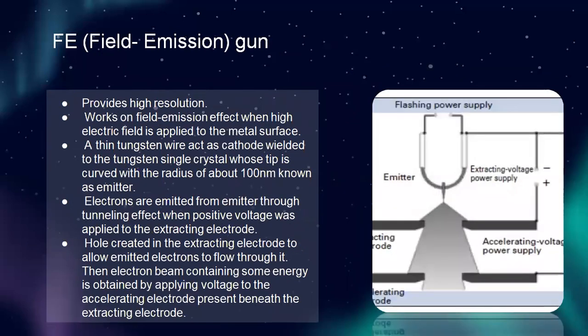The second type is the field emission gun, which provides high resolution work based on the field emission effect. When a high electric field is applied to the metal surface, a thin tungsten wire acts as cathode welded to a tungsten single crystal whose tip is curved with a radius of about 100 nm, known as the emitter. Electrons are emitted from the emitter through the tunneling effect when positive voltage is applied to the extracting electrode. A hole is created in the extracting electrode to allow emitted electrons to flow through it. An electron beam with a certain energy is obtained by applying voltage to the accelerating electrode beneath the extracting electrode. In the diagram: extracting voltage power supply, accelerating voltage power supply, and emitter.